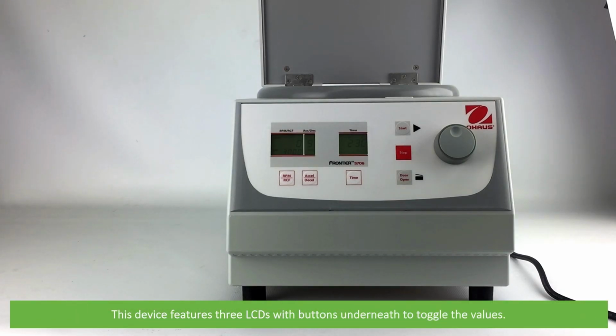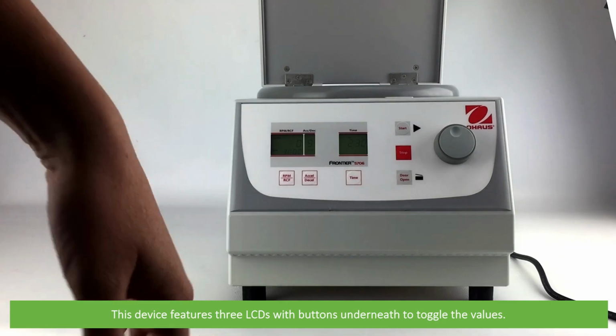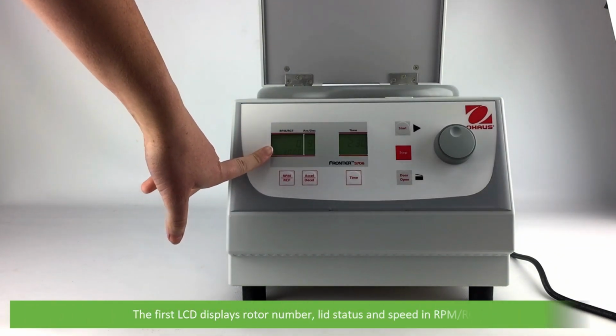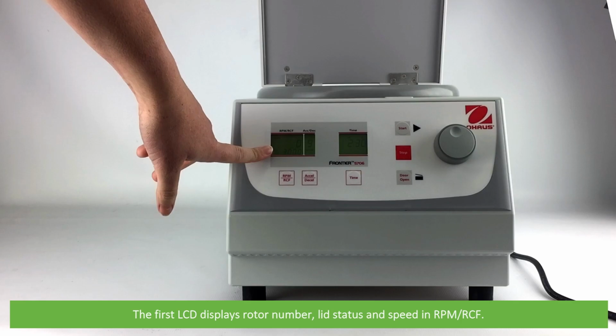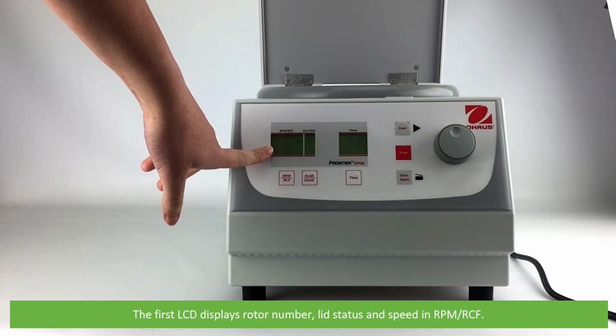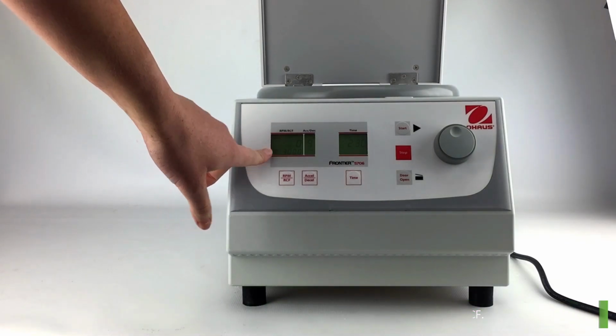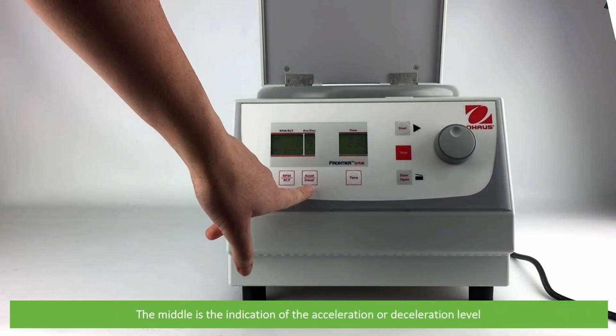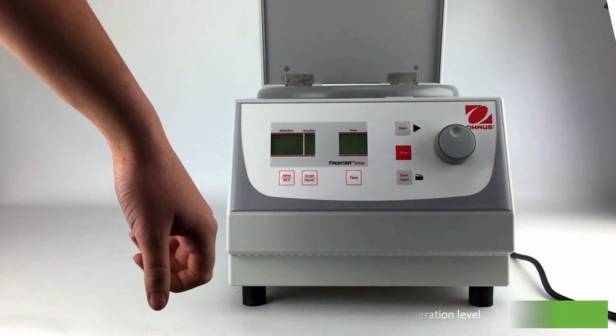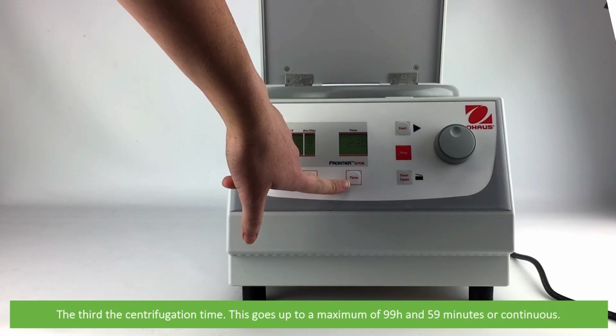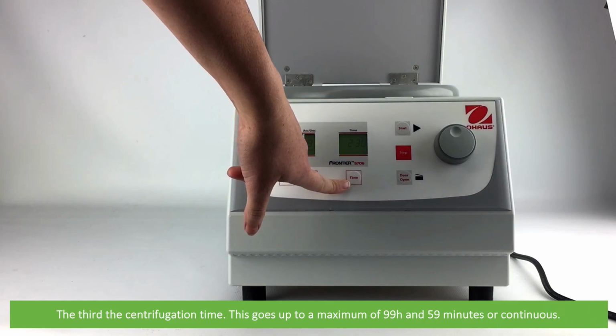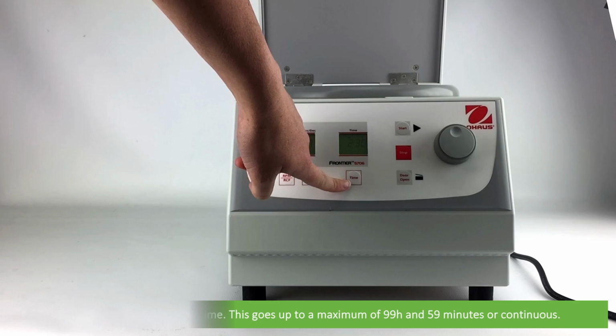This device features 3 LCDs with buttons underneath to toggle the values. The first LCD displays the rotor number, lid status, and the speed in revolutions per minute or relative centrifugal force. The middle is the indication of acceleration and deceleration level. The third is centrifugation time, which goes up to a maximum of 99 hours and 59 minutes, or can be set to continuous.